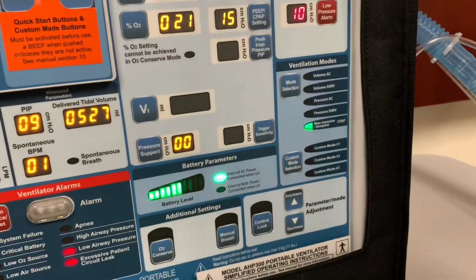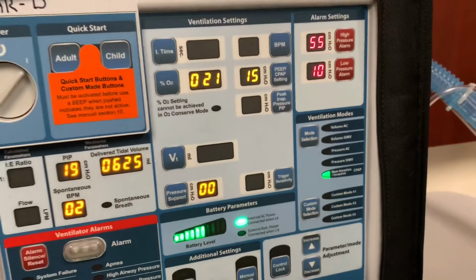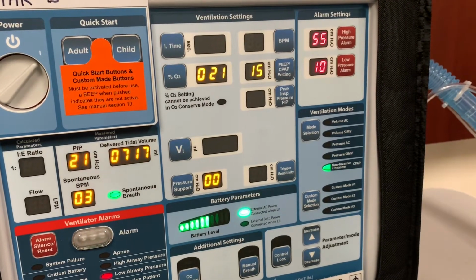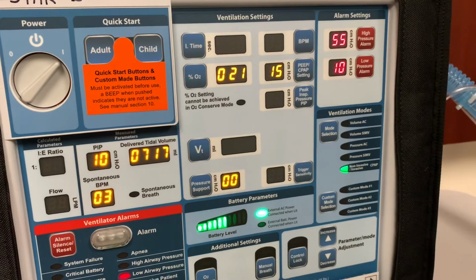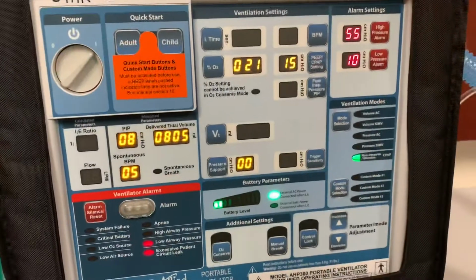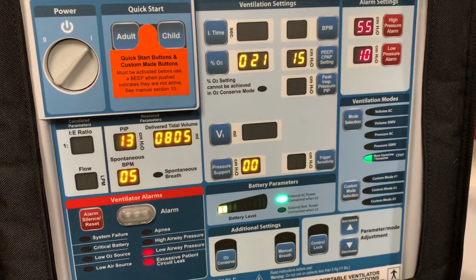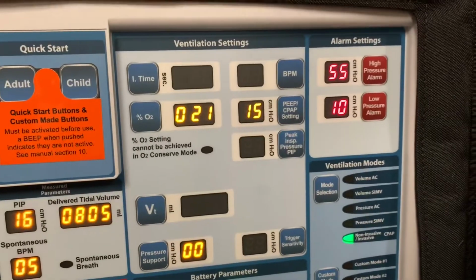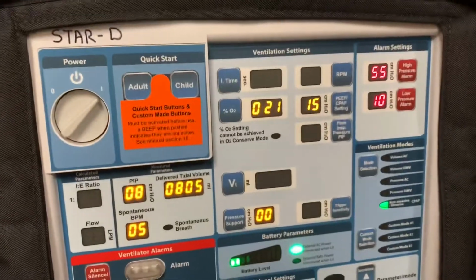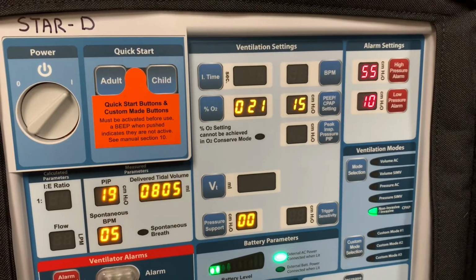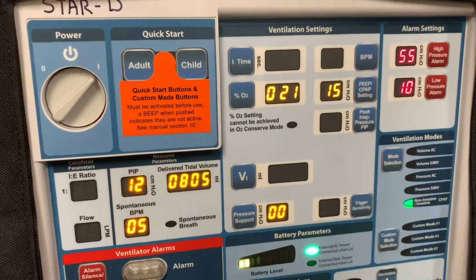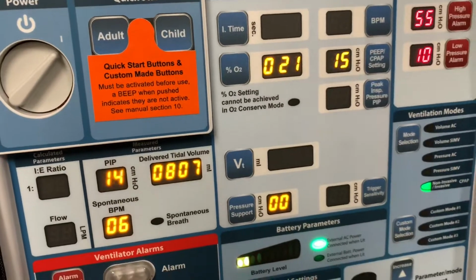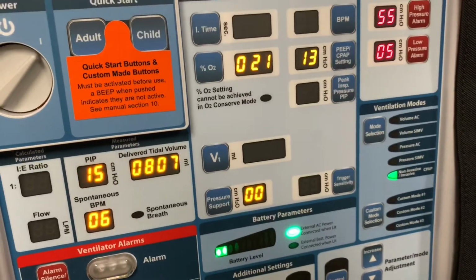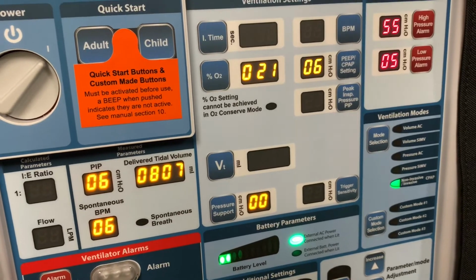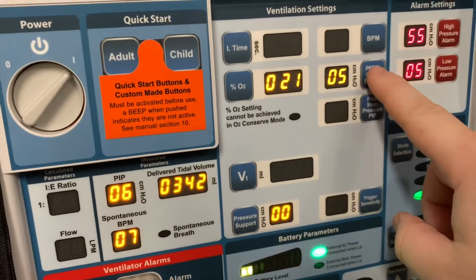Now that we've changed it over to the CPAP mode, you may be interested in perhaps putting this person on CPAP with pressure support, or more commonly known as BiPAP. CPAP with pressure support simply requires that the pressure support be in excess of the CPAP setting. Now, 15 is somewhat of a high CPAP setting if you're going to have that with pressure support. So in this case, we're going to go ahead and decrease our CPAP setting down to 5. Once again, it's flashing. I'm going to lock it in.